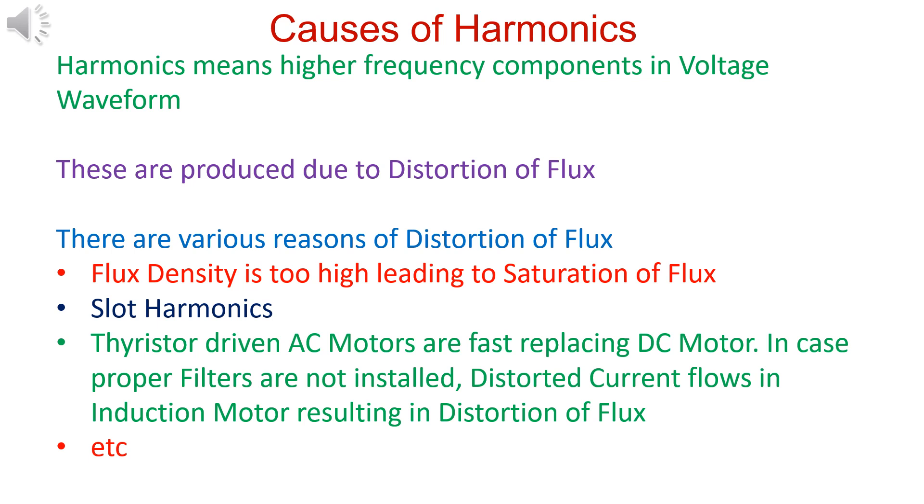Harmonics in voltage are due to distortion in voltage waveform, which in turn is due to distortion of flux. Flux is distorted due to various reasons, e.g. saturation of flux, slot harmonics, improper filters in thyristor drives, etc.